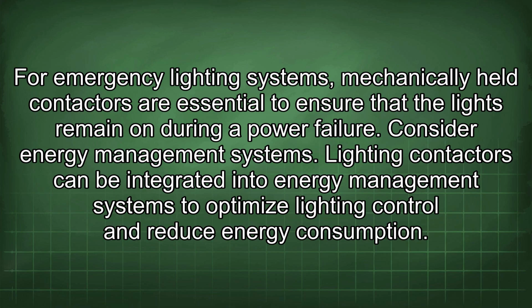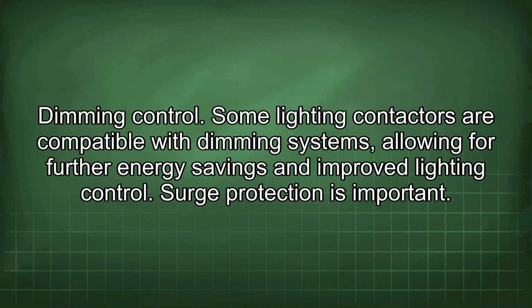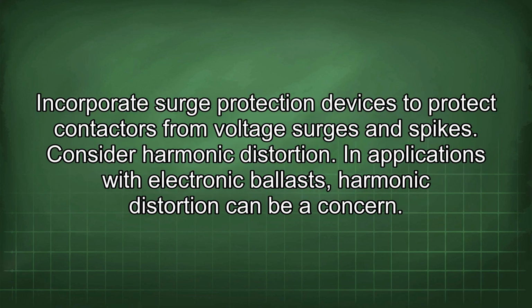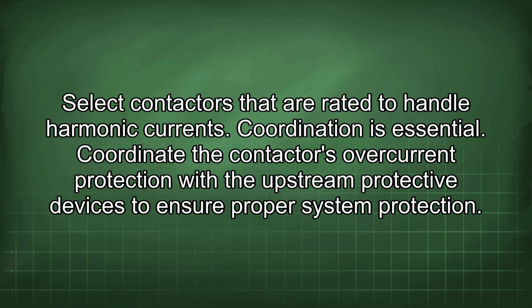Consider energy management systems. Lighting contactors can be integrated into energy management systems to optimize lighting control and reduce energy consumption. Dimming control. Some lighting contactors are compatible with dimming systems, allowing for further energy savings and improved lighting control. Surge protection is important. Incorporate surge protection devices to protect contactors from voltage surges and spikes. Consider harmonic distortion. In applications with electronic ballasts, harmonic distortion can be a concern. Select contactors that are rated to handle harmonic currents. Coordination is essential. Coordinate the contactor's overcurrent protection with the upstream protective devices to ensure proper system protection.